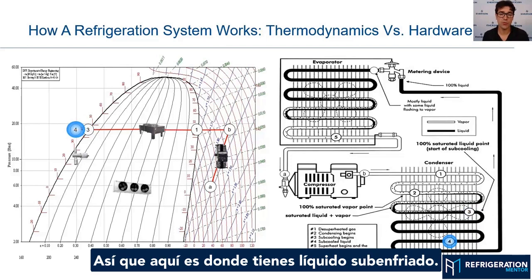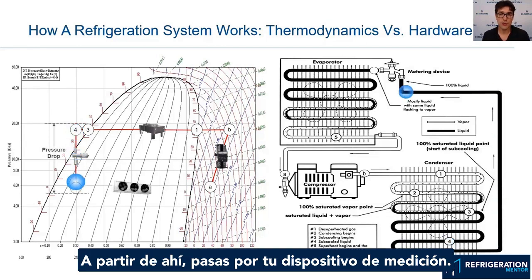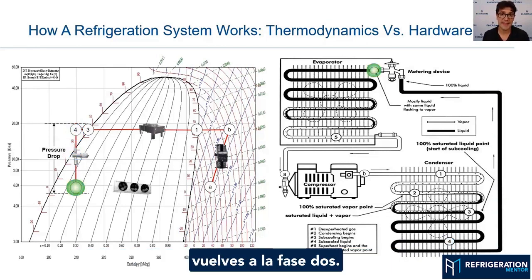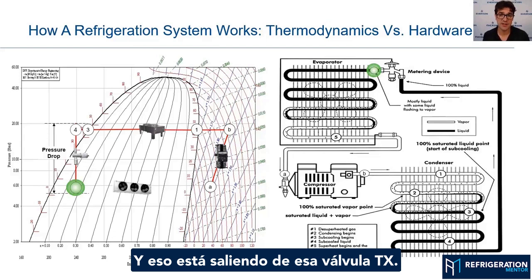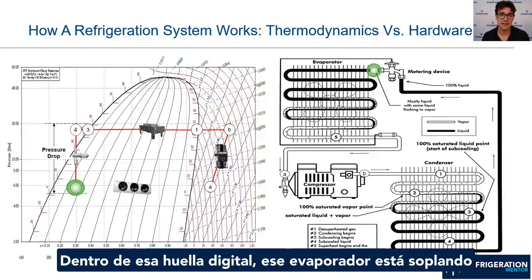Anything on top of that now is your subcooling, so this is where you have subcooled liquid. From there, you go through your metering device. You have that pressure drop, which pulls you back into the 2-phase — you have both liquid and vapor, flashing out of that TX valve.